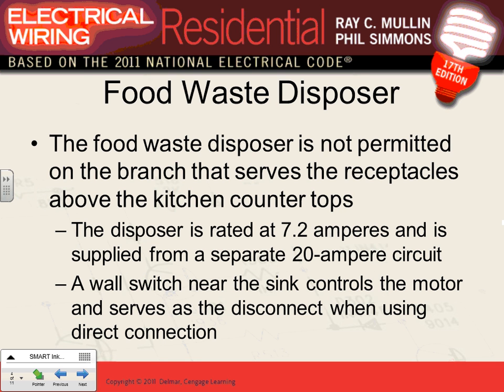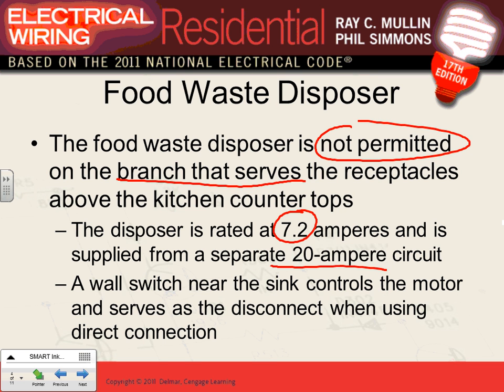Okay, the most important thing I want you guys to highlight: not permitted. These are not permitted on the small appliance branch circuits in the kitchen. You can't plug in from the 20 amp branch circuit that feeds the kitchen. Remember, dedicated small appliances, they're not permitted. So if they're not permitted, then you have to provide a dedicated circuit. The disposal, here's a typical disposal for these guys. Garbage disposal 7.2. What we provide for it is a 20 amp. Let's do the math on that. Let's just do the math and give you an idea of how we do this. So if the full load amp, say from the NEC, let's assume this is from the NEC.